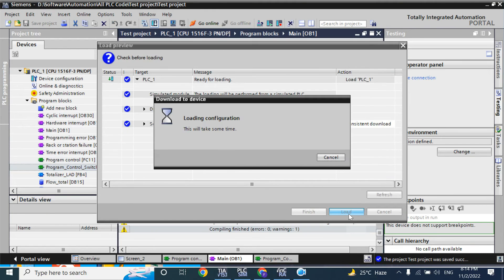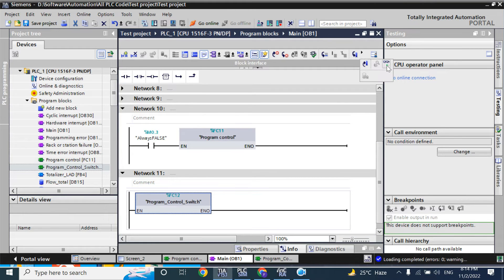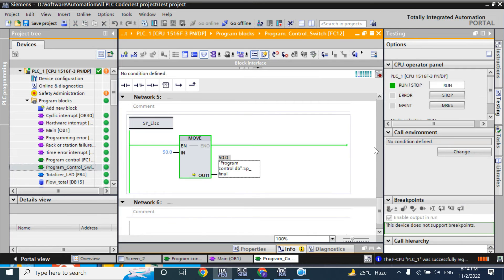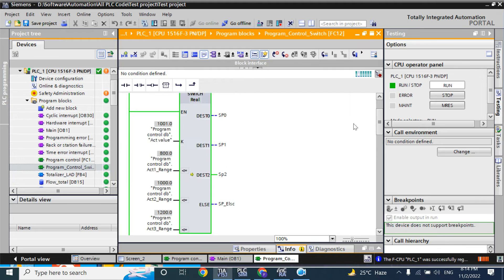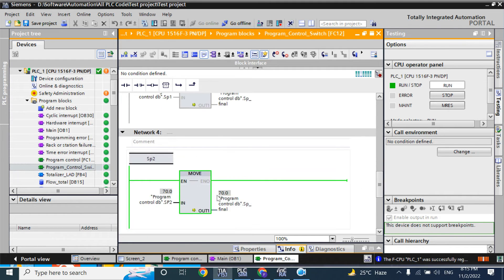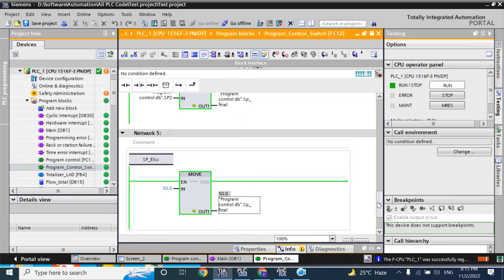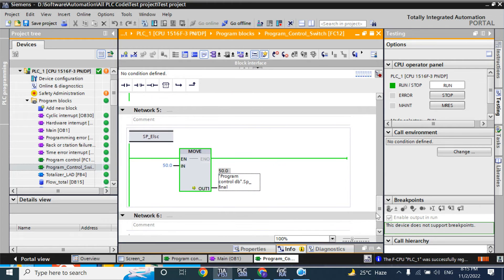After downloading, here you can see this network is not scanning, and this one is scanning. The value is now SP100 — it should be SP2. Only this one should be scanning, but it is scanning the other networks too. Because of that, the program setpoint: when this network is scanned the value is 70%, and when the else network is scanned the value will be 50%. So the motor speed will switch between 70% and 50% — that is wrong.